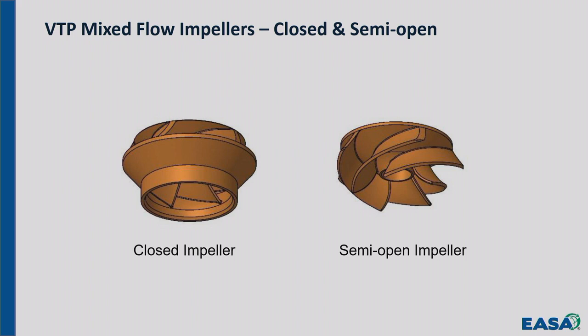Okay? The open impeller does not have that, and as this impeller is lifted up, part of the lift adjustment will lift where that impeller is running in relationship to the stationary element of the pump. It opens up the clearance between the face of the vanes and the wear plate that's next to them. So you can see if I raise or lower this impeller 50 thousandths, it's going to have a much bigger effect than if I raise or lower this impeller 50 thousandths. So some of you may be aware, or had heard, that, hey, if the motor pulls high current, I can lift the pump shaft up some and take some of the load off the motor. How many people have heard that?